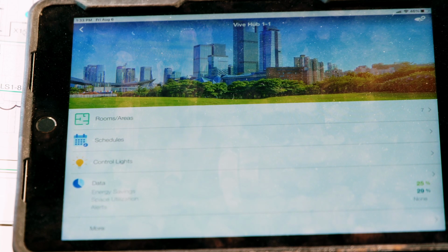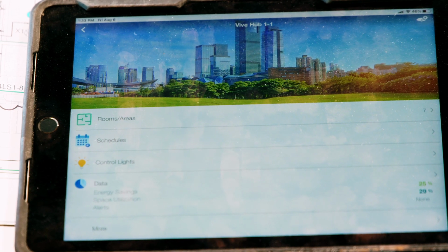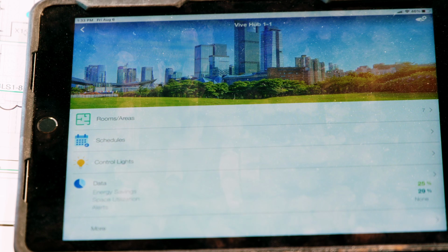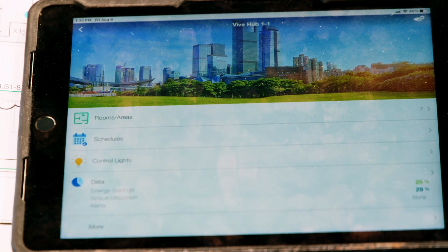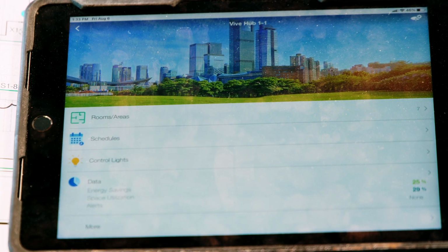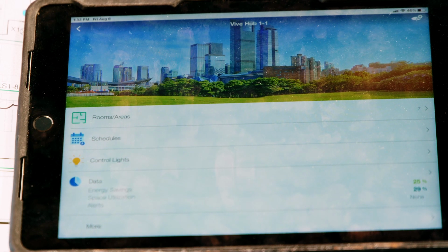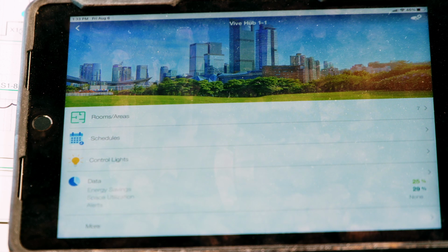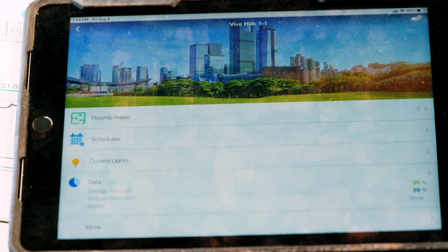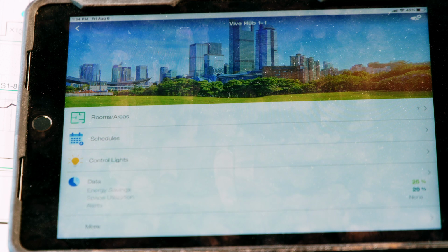It's already in preparation that all the hubs are going to be networked together to a network switch, and if you can set up a server, the Vive View software could be loaded on that server, and all this data from all these hubs can be pulled in. All we would need is IP addresses for those Vive hubs, and then you can lay this whole system out by floors. Everything I put in pulls right into the software, and then you can take the floor plans, import them into the software, and populate it from there. Then you can see the fixtures and all that, and the system becomes manageable from any desktop connected to your network, so you don't have to be in the building with an iPad going to all the different places. So I would definitely look into seeing if that's feasible to install here.